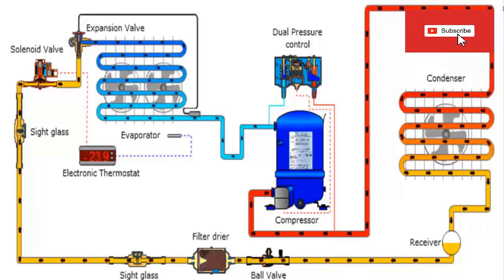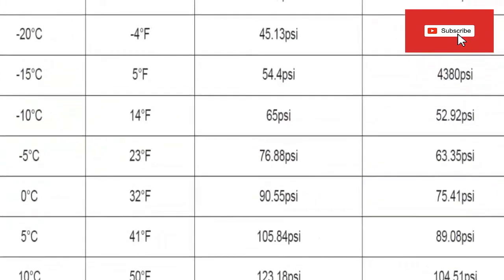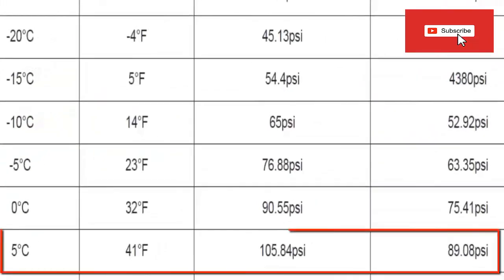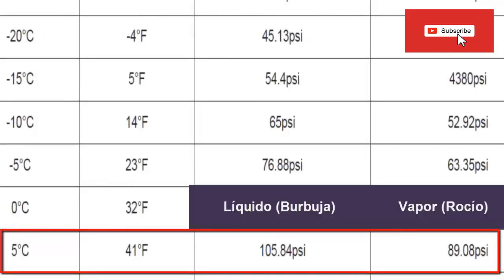For example, for an evaporator temperature of 5 degrees Celsius, about 41 degrees Fahrenheit, according to the table, there are two pressure values: liquid or bubble pressure equal to 105.84 psi, and vapor or dew pressure of 89.08 psi.